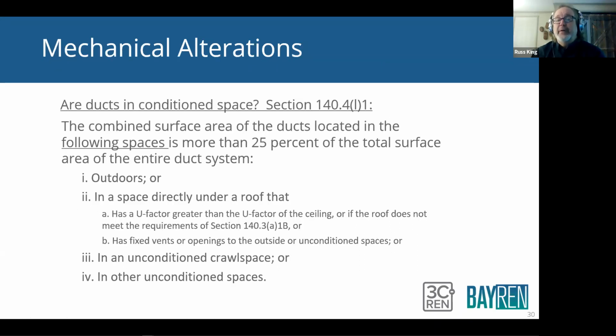The first thing you have to ask yourself, or one of the important questions to ask to determine whether or not you have to seal the ducts, is: are they in conditioned space or not? So section 140.4(l)1: the combined surface area of the ducts located in the following spaces is more than 25% of the total surface area of the entire system. So you have to do a little calculation to figure out the square footage of the surface area. Sometimes it's really easy to tell, sometimes it's not so easy. But if more than 25% is outdoor, so it's on the roof, or just suspended through an unconditioned warehouse or something like that, that's considered outside or unconditioned space.